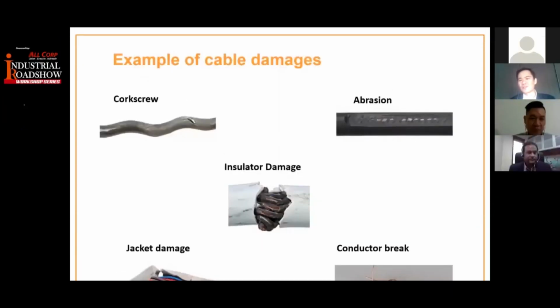Here are examples of cable damage that occurs over time, or immediately, when the wrong cables are chosen. You get a corkscrew effect, where the cable looks like a little worm, because the cable jacket wasn't properly selected, causing abrasions. You may also get insulation damage from the jacket damage rubbing the insulator, which can result in machine failure, short circuits, or blown equipment. Eventually conductor break occurs, and on automation equipment you'll see a signal on/signal off effect because of this conductor break.